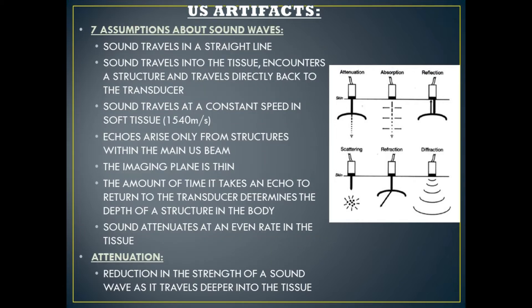Let's talk about the assumptions that an ultrasound machine makes about sound waves. Number one, sound travels in a straight line. Number two, sound travels into the tissue, encounters a structure, and travels directly back to the transducer. Number three, sound travels at a constant speed in soft tissue — 1540 meters per second.